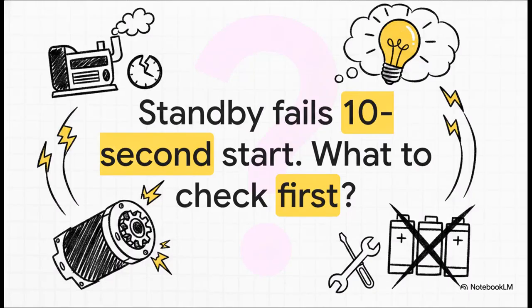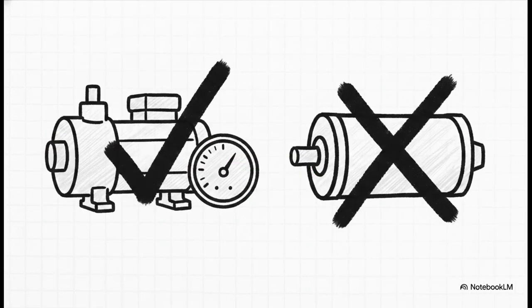Okay, let's pause for a quick real-world scenario. Imagine you're managing a facility. Your standby generator fails its mandatory 10-second start window during a routine test. Let's say it takes 14 seconds instead. What's the very first system you'd suspect? I mean, usually most people are going to guess the starter motor or maybe degraded batteries. Well, actually, the real answer is the continuous pre-lube system and its pressure sensor. Think about it. A standby application is supposed to have oil already circulating and ready at all times. So a slow start points directly at a pre-lube fault. The engine's ECM literally will not allow the crank to happen until pressure is confirmed. So if it's taking too long, it's highly likely your pre-lube pump has failed, not your starter.